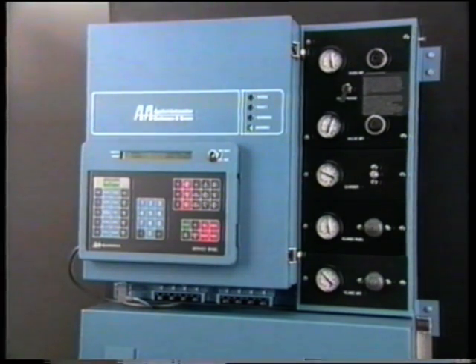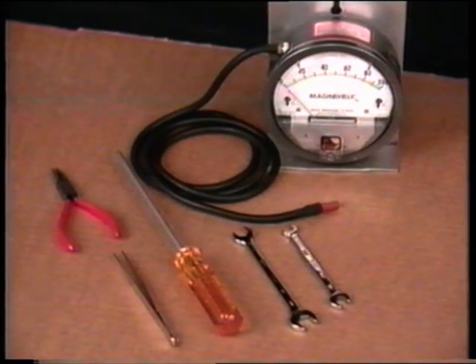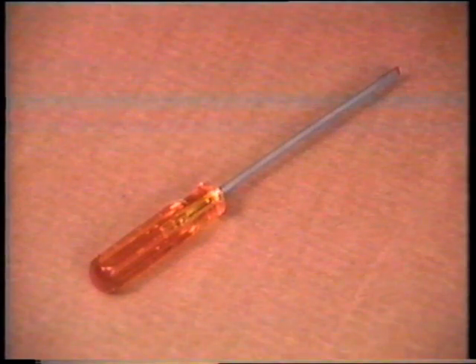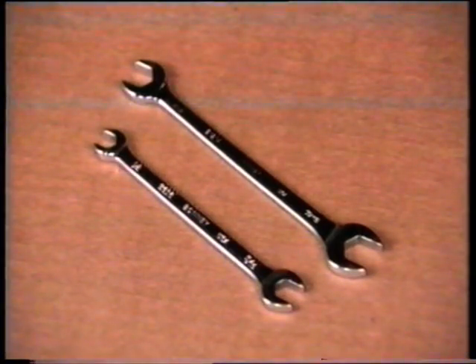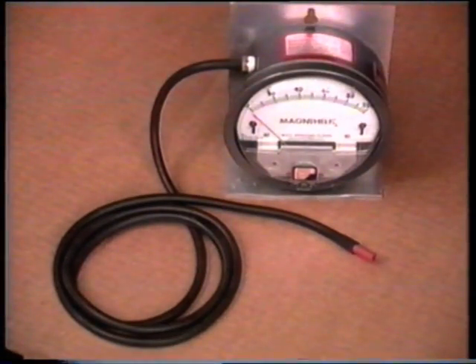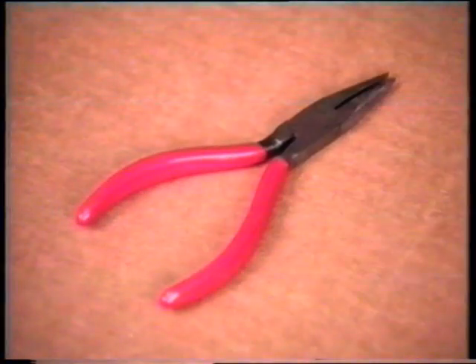This gas chromatograph contains an intercolumn thermistor detector. Intercolumn detectors and their function are discussed in your workbook. Some tools you'll need to maintain the flame ionization detector are a screwdriver, open-end wrenches, magnehelic flow meter, small tweezers, and 6-inch needle nose pliers.